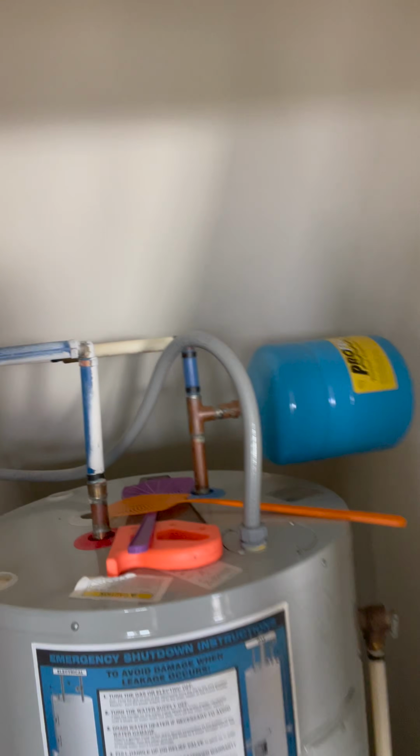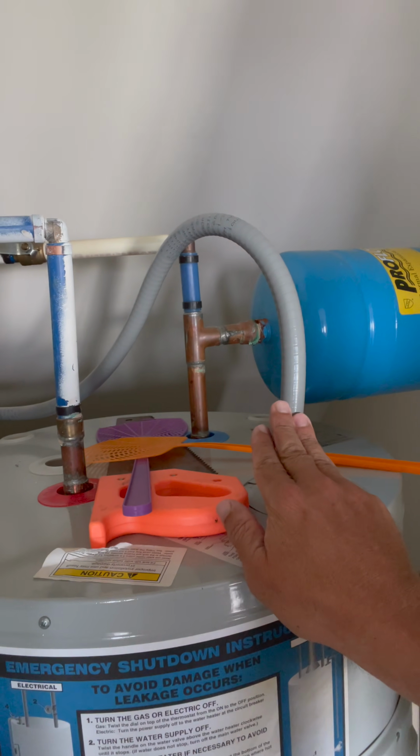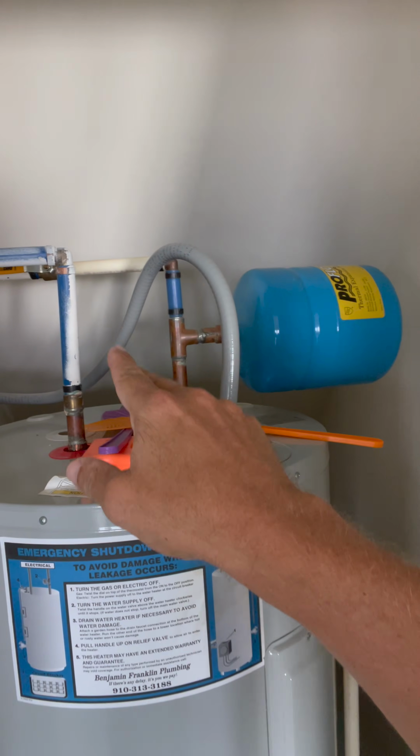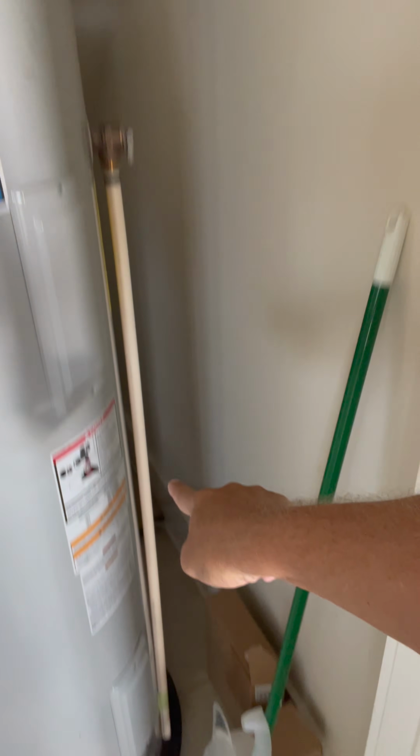And the hot water source, it's an electrical hot water tank. Here's the electric line coming in. Cold, hot, TPR valve discharging to a catch pan and there's water in the catch pan. So something is leaking. I don't think it's the TPR valve. I think the tank is leaking, but I'm not sure, and it actually doesn't matter. That water should not be in the water leak catch pan.